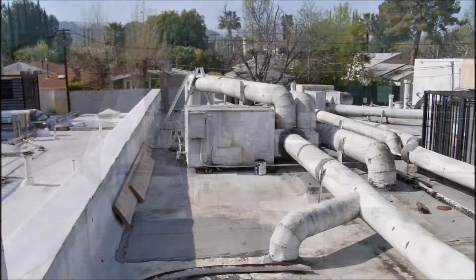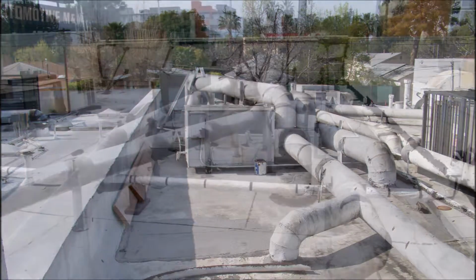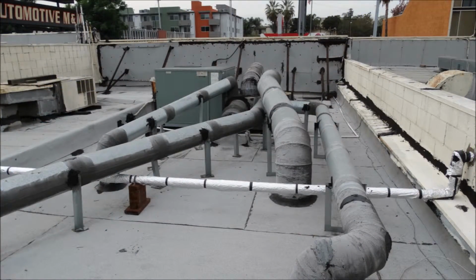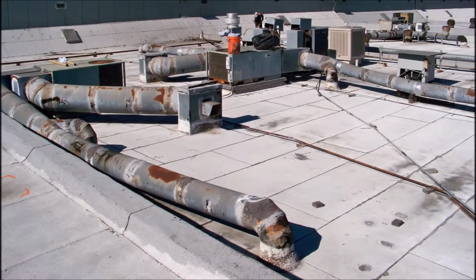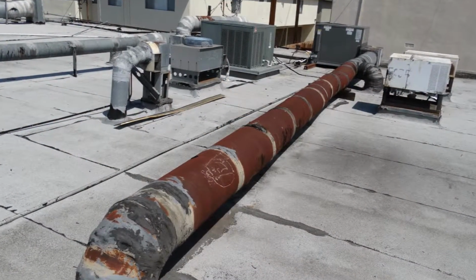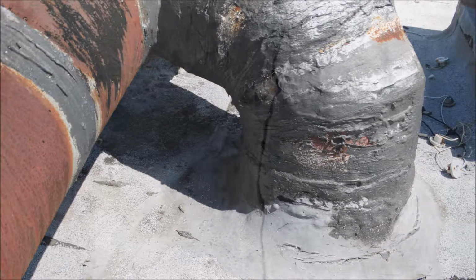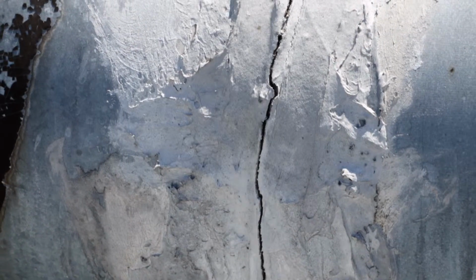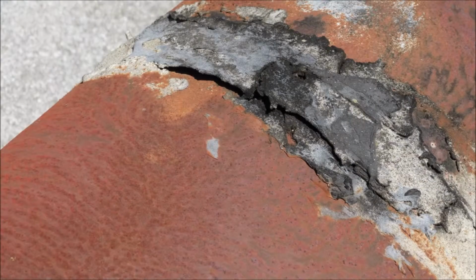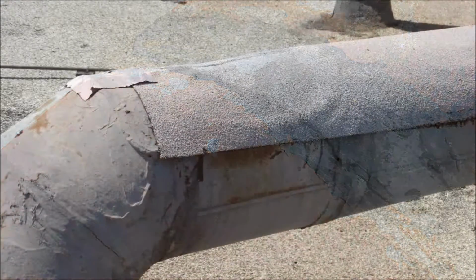These duct joints, when initially installed, were waterproofed by the installers using standard and proper sealants. But over the years, these joint seals break down from heat and UV rays, eventually losing their water integrity. As the metal expands and contracts, the waterproofing and air seals develop splits and holes, allowing water into the duct and eventually into the building.